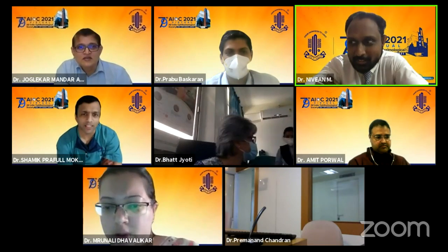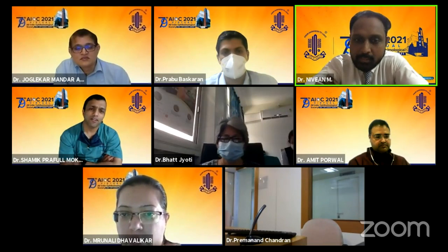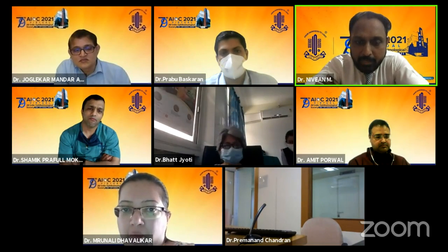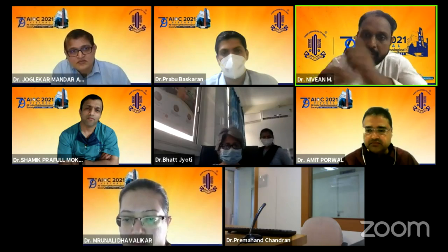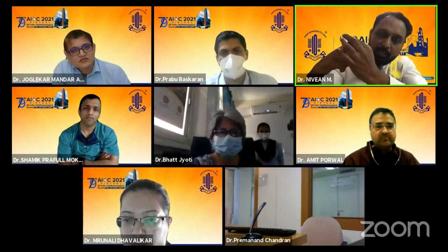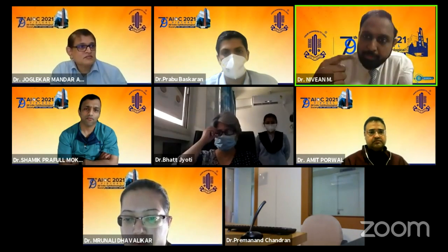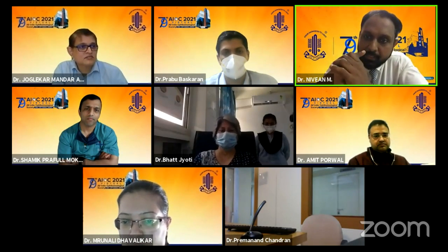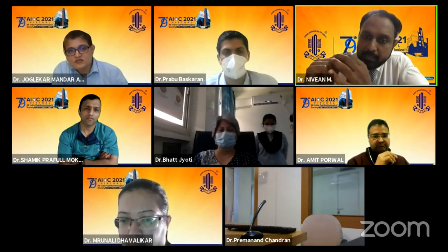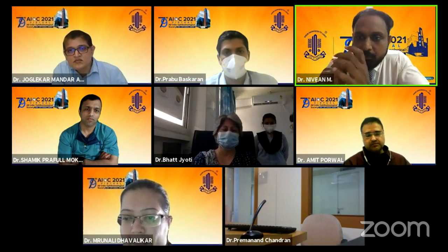Right. But then the wound is always going to be leaky, isn't it? That sclerostomy also. So for the 23 gauge, we have made those T junctions, that round thing, with the diameter in such a way that it snugly fits in. Even though you're using the forceps, it might expand, but this fits in so that there is no leakage. Some people suggested we make it thinner, so whether it can go to a 25 gauge. But when we make it thinner there is a gap, and that can cause wound leakage and hypotony. So we wanted to make sure that it fits tightly in the sclerostomies.